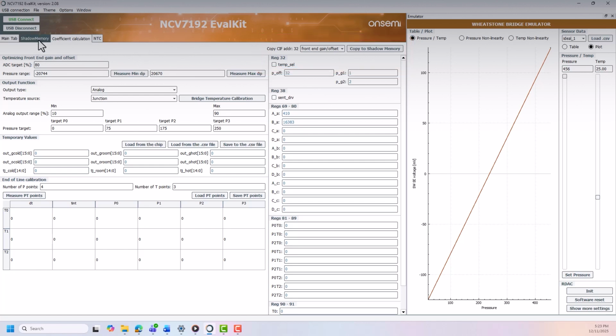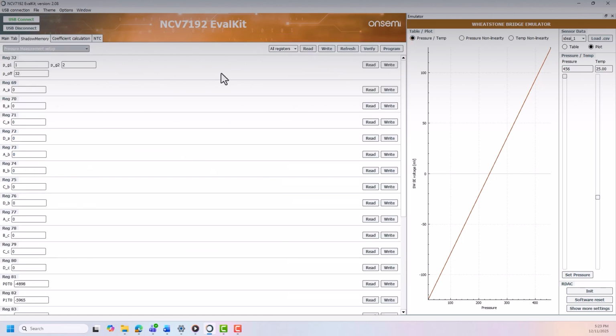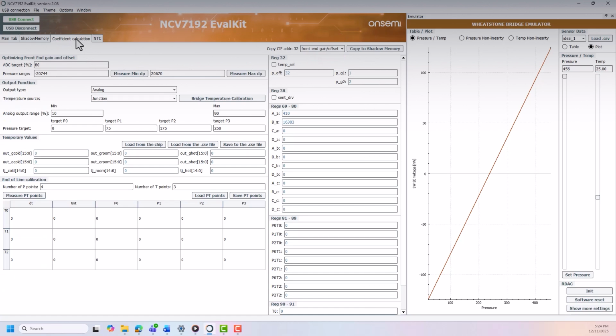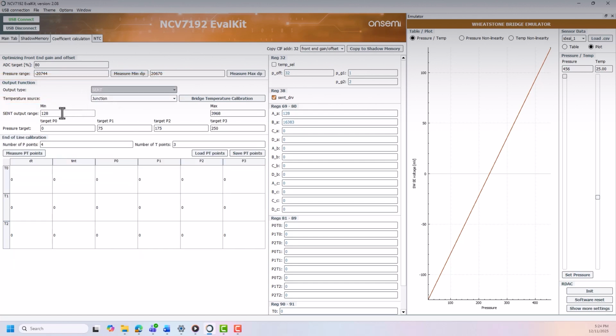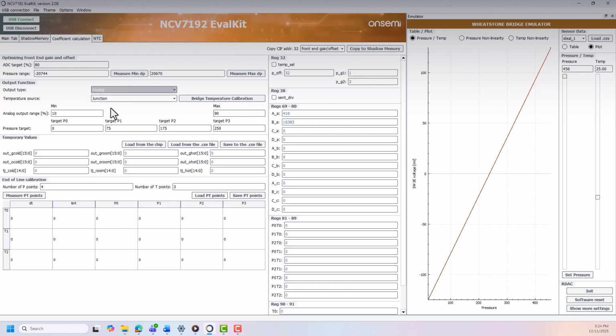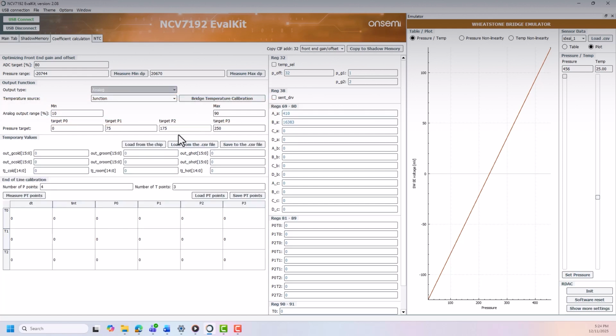Go to Shadow Memory tab and click to Write button. Input stage is now properly set. Second step during calibration is to calculate coefficients for the DSP. By this menu, we choose Device Output Type. For sent output, we need to specify just minimum and maximum code matching with lowest and highest pressure. For analog output, you need to specify analog output range in percentage, matching lowest and highest pressure. And you can also see that for analog option, there is extra table called temporary values.